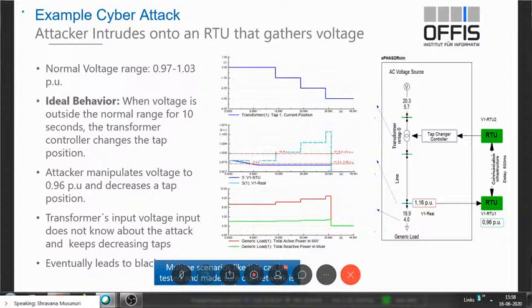So the controller always assumes that the voltage is much lower, and it starts behaving because that's how it's designed to. It starts changing the voltage tap of the transformer, reducing it, continuously changing the tap position. But since the hacker is introducing this at the RTU level, the sensing element feeding into the controller still feels that the voltage is at 0.96 only. So the controller keeps trying to reduce the tap because the hacker has hacked in between, and eventually, beyond a certain level, the system collapses.